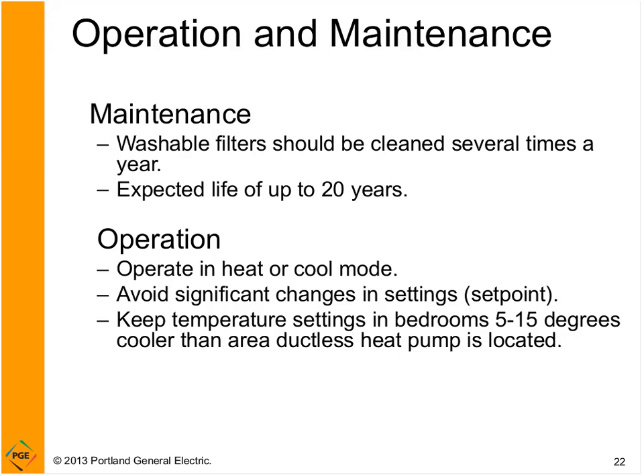And operation: the operating modes are generally heating, cooling, or auto. For most efficient operation, we suggest operating in heating or cooling mode according to whatever season you're in, and avoiding significant changes in settings. Heat pumps are a little bit different than a wall heater or a baseboard, for example. Since heat pumps rely on bringing heat from the outdoors to heat the indoor space, it takes a little more time for the temperature to rise. So if you had a really big setback, let's say 10 or 12 degrees, it might take a little bit of time for the temperature to recover. It should still be fairly quick, but it's something to keep in mind: maybe not have as deep setbacks as you would with a zonal electric system.